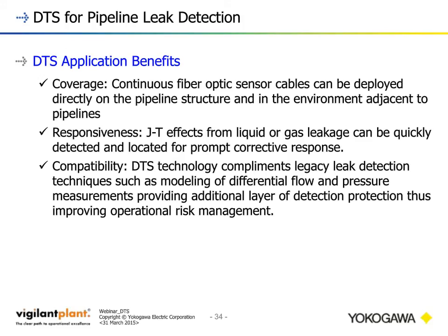So again, in pipeline and storage applications, we've got the continuous sensor deployment, the Joule-Thomson effects, the delta T that happens when a liquid or gas or a multi-phase leak begins is quickly and easily and directly monitored, the locations identified immediately.